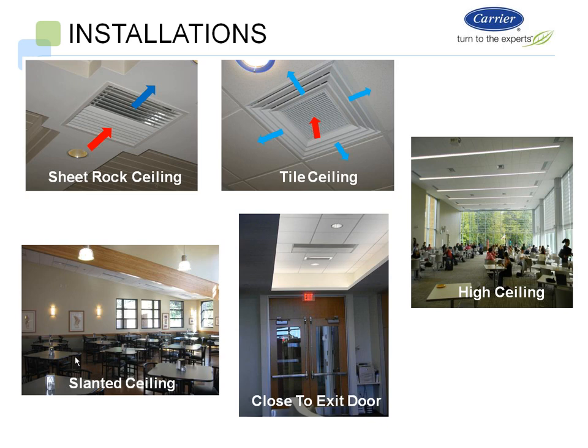And then if you look further to the right, another one is a high ceiling application. A traditional chill beam today would be no more than 12 foot high, and they're very clear on the specifying of that. That's an actual install using the one-ways on the perimeters, and you can see all the load from the window load there, and the all-ways 2x2s in the interior, and that's a 21-foot ceiling. So that's about where we're recommending you can go with these units. So a typical higher ceiling, these can be installed also, so you don't have to worry too much there.